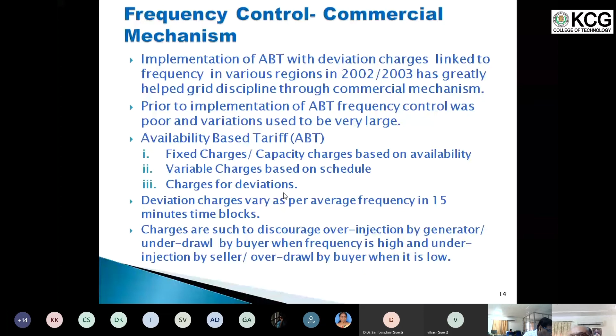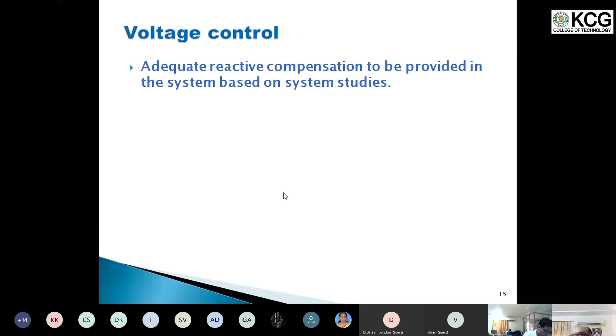And voltage control: from the planning stage, you provide adequate reactive compensation into the system, and for controlling the voltage, the grid operators can use the shunt reactors at 400 kV and 765 kV. You provide shunt reactors for controlling the voltage. Those can be switched in or switched out. For voltage control, you can also change the taps of the interconnecting transformers. So these are the measures, and then the AVRs have to be in service.